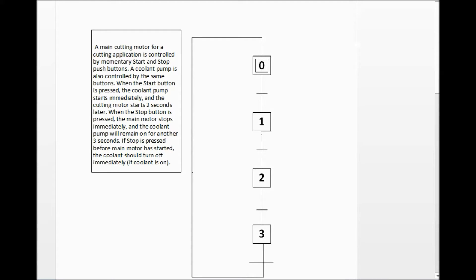Now we're going to develop a sequential function chart for this cutting and coolant control application. I've created a function chart here. When we see a box, that's a step — outputs happen at steps. We have steps 0, 1, 2, and 3. The crosshair symbols are called transitions — that's what needs to happen before the process can move to the next step. We have two inputs: a start push button and a stop push button. We have two outputs: a cutting motor and a coolant pump.